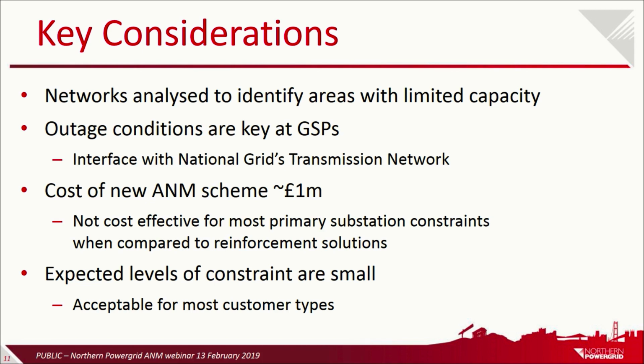So taking those into consideration, we've analysed across our networks looking for the areas with limited capacity. I'll skip the first point for a second, but the cost of building a new ANM scheme like Driffield is of the order of about £1 million, taking into consideration all the building blocks that Ian's described. And that generally makes it not cost effective for small constraints that may be at a primary substation. Now, the cost of completely rebuilding a primary substation is of the order of about £4 million. But if you've only got a partial constraint within that site, the reinforcement solution will generally be cheaper than that. And the differential in price wouldn't make ANM on its own attractive. But where the cost of the reinforcement is significantly higher than that, then ANM really starts to come into its own.